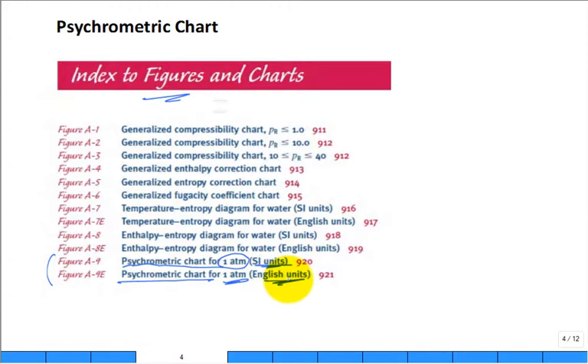So the psychrometric chart in our textbook is in the appendix, and it's back here. The psychrometric chart at 1ATM in the SI units or the psychrometric chart at 1ATM for the English units. If you're designing stuff in Houston, Corpus Christi, you're at sea level, guess what? No problem. You want to move to Colorado, maybe some resort part of Colorado and work as an engineer, and you're a mile high or higher, don't use the 1ATM chart. Go get the high altitude chart. Or actually rely on the computer, which adjusts for your actual altitude. But all of this is for 1ATM.